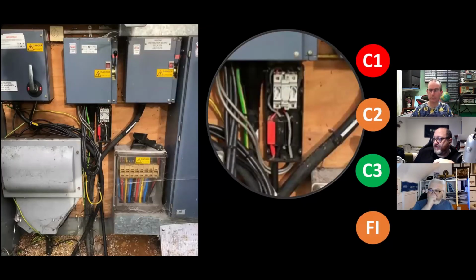You're all right. Everyone's gone for C1 really. 57%. Pretty straightforward. It's that obviously live parts right in the way and can't really avoid them. So 29% have gone C2, 7% C3, 7% FI.